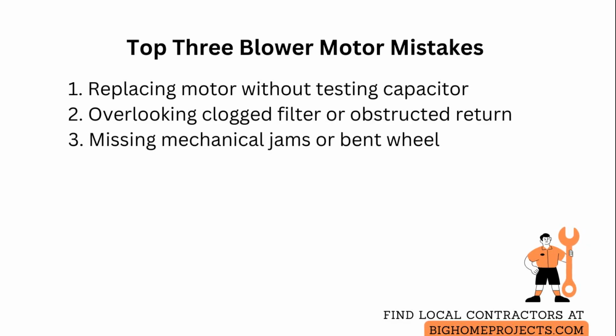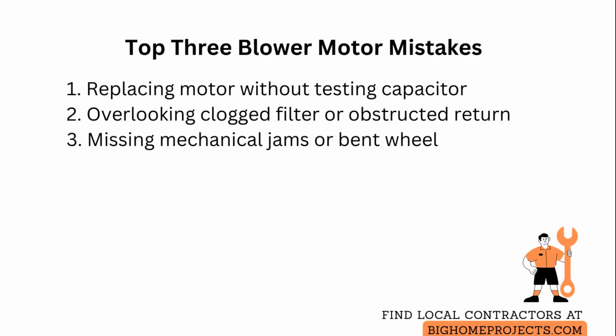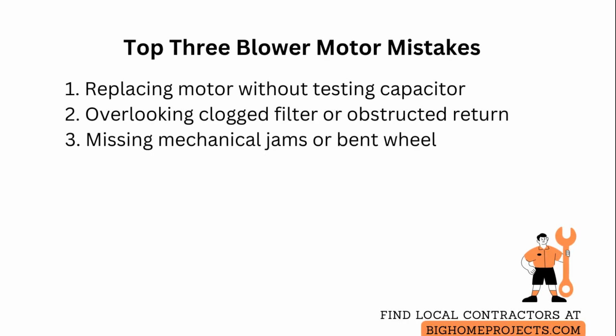Technicians sometimes assume a no start is purely electrical and miss mechanical jams such as debris or a bent blower wheel, so spin the wheel by hand to verify free movement and clear any obstruction.